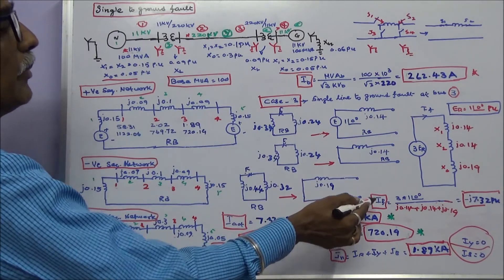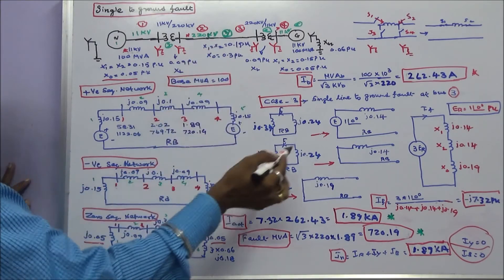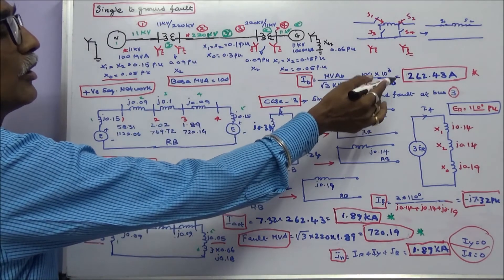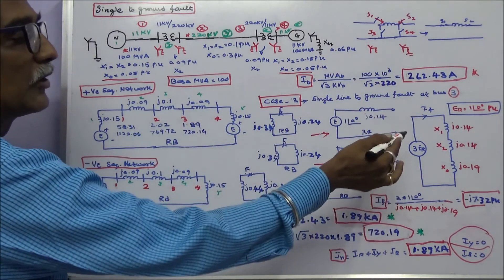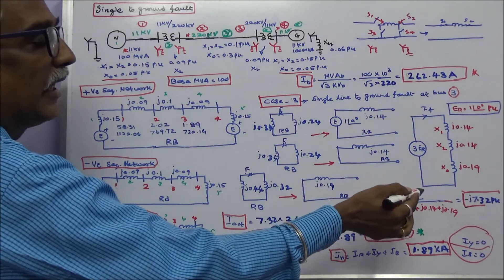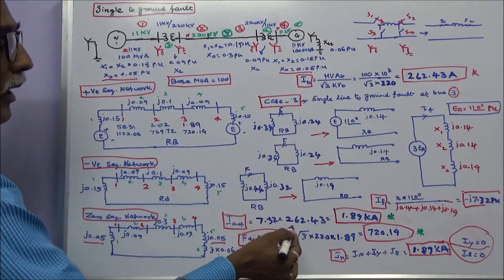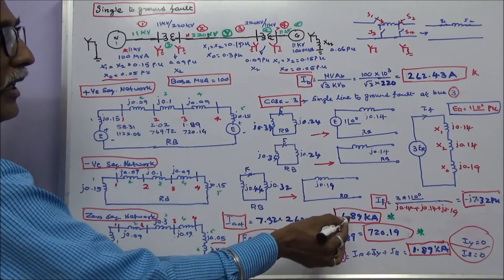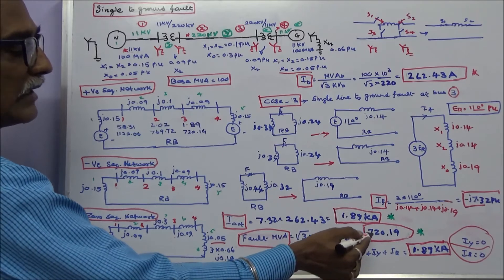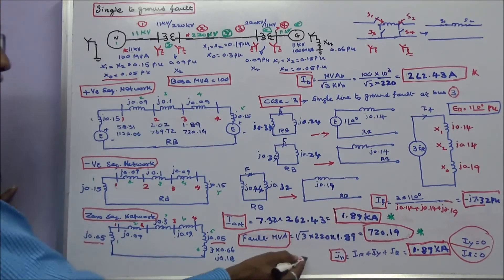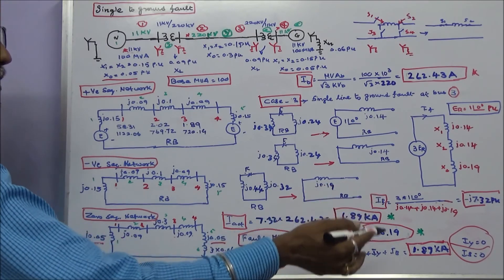We can easily calculate the fault current. Fault at bus 3 at voltage 220 kV. Base current is 100 times 10³ divided by root 3 times 220, equaling 262.43 amps. Fault current equals 3 times E divided by X1 plus X2 plus X0, giving IF equals minus j7.32 per unit. Actual fault current is 7.32 times 262.43, equaling 1.89 kilo amps. Fault MVA equals root 3 times 220 times 1.89, equaling 720.19. Neutral current IR equals 1.89 kilo amps; IY equals 0, IB equals 0.